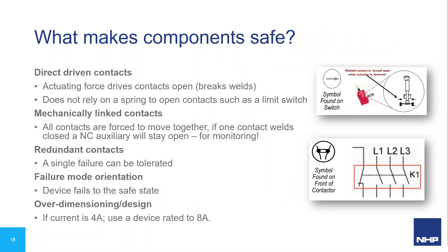What specifically makes safety devices suitable for safety control systems? Direct-driven contacts operate by direct mechanical action — the operation of the contacts is directly coupled to firm mechanical motion, not springs or electrical actuation. When you press the actuator of a limit switch, the sheer force directly opens the contacts. So if contacts were stuck closed, the force from the actuator is enough to forcibly break them open, making them significantly more reliable.